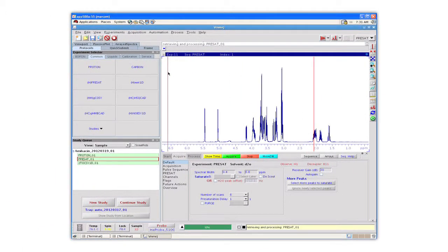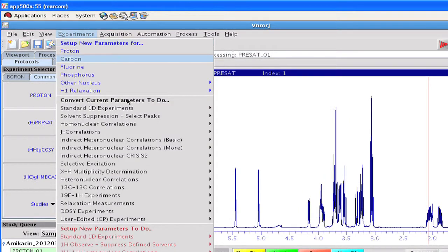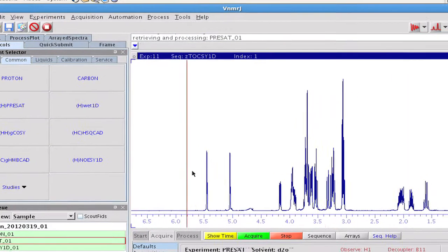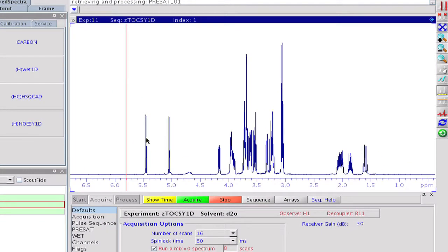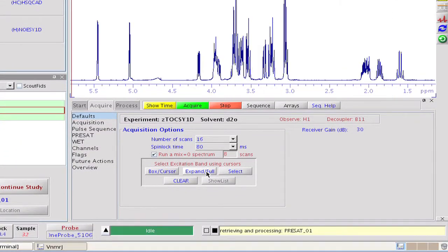A proton spectrum with solvent pre-saturation has been collected and serves as a starting point in our setup procedure. First, we convert the current parameter set to be ready for the selective 1D TOCSY acquisition. By doing so, we import all sequence-specific parameters while keeping all the others that have been optimized on the pre-sat spectrum. The spectral window, for example, or the pre-saturation conditions, just to mention a few.